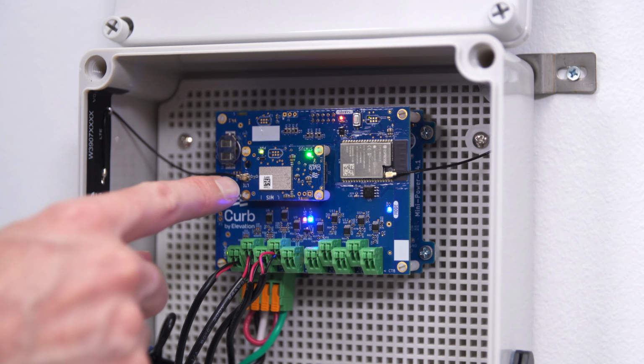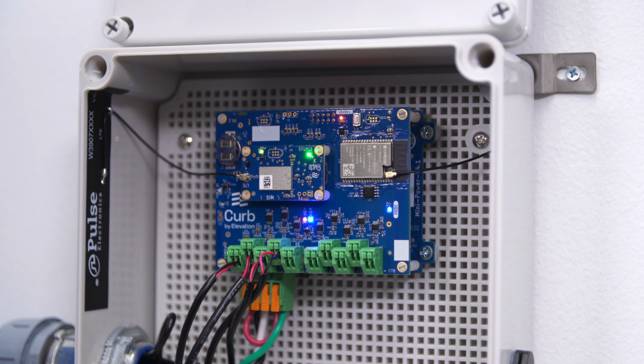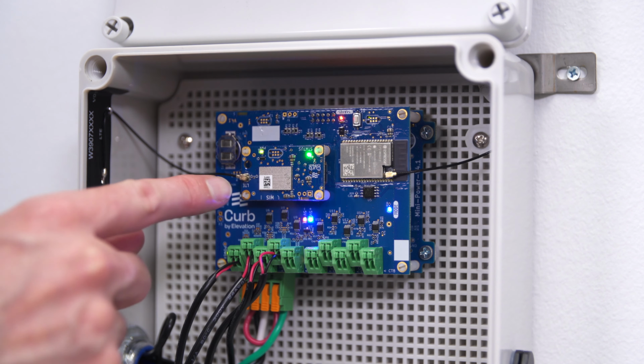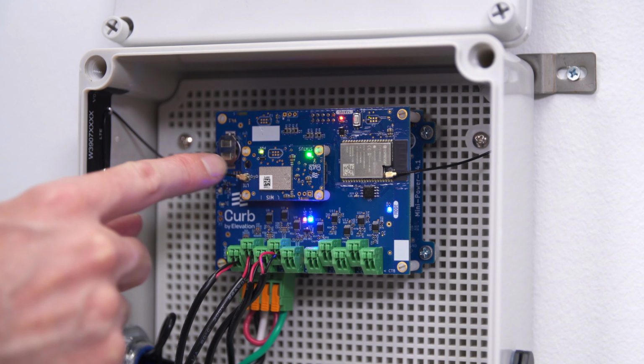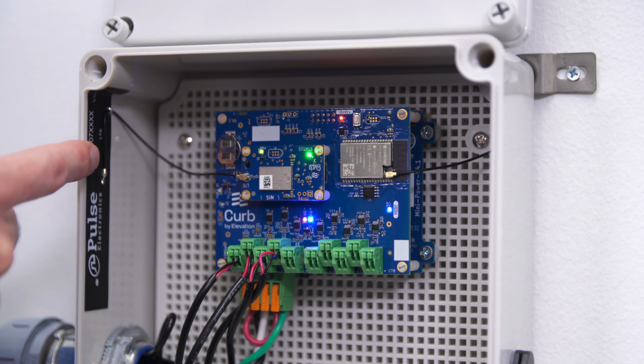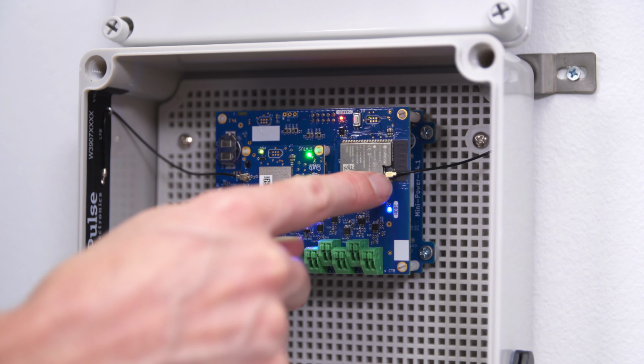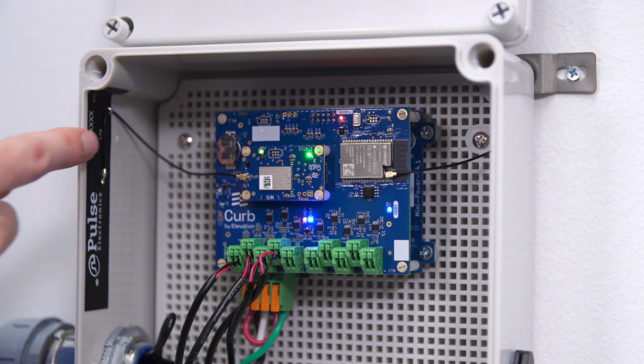It's worth noting there are two different antenna systems on the Curb device. This is the cellular connection that goes to the cellular antenna, and this is the Wi-Fi connection. We want to ensure that both those antennas are at least 6 inches away from any metal boxes, and also that they are at least 3 feet away from the floor.